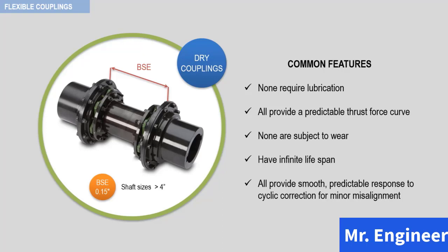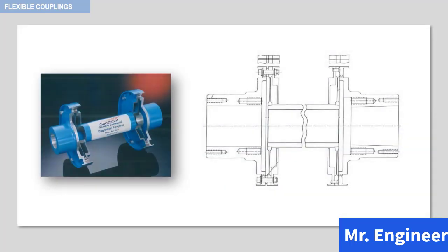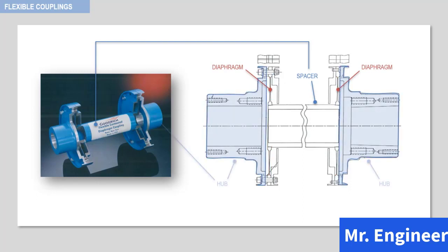A cutaway view of a single diaphragm spacer type coupling is shown here. This coupling is made of a spacer, diaphragms, and hubs. This type of coupling is commonly used for critical applications where axial end float values are less than 0.125 inches. If end float values are greater than this limit, a convoluted diaphragm or multiple type diaphragm must be used. During disassembly, care must be taken when removing the spacer to not scratch or dent the diaphragm element, as even a tiny scratch that penetrates the protective coating can cause a diaphragm failure.